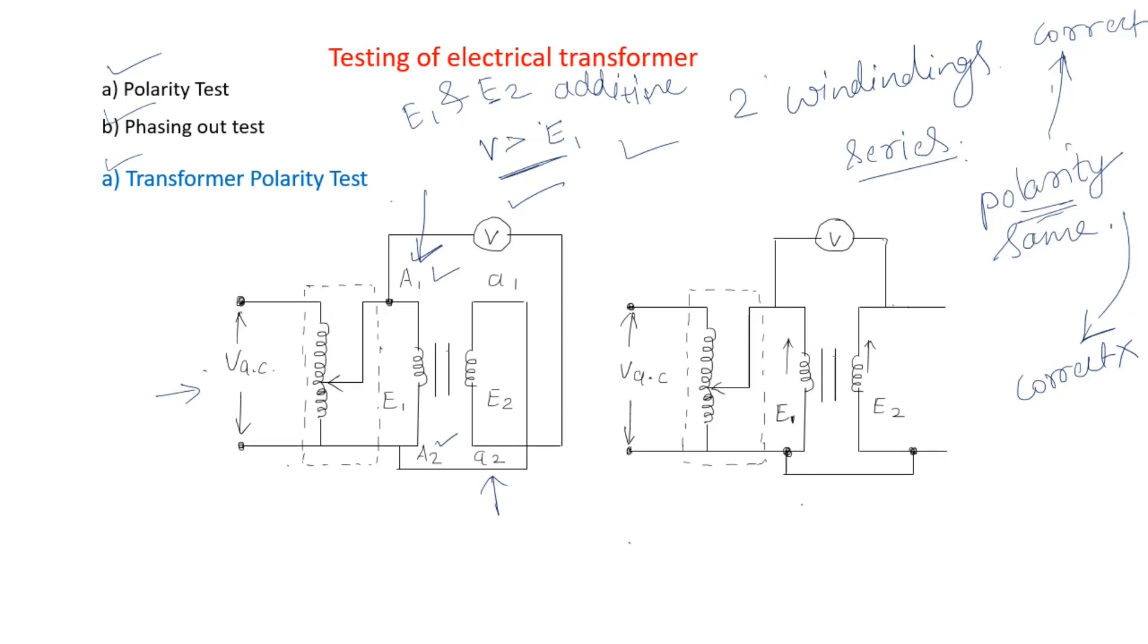So to confirm the correct polarity, in this case V should be less than E1. So in this case, to confirm the correct polarity, V should be less than E1. This is how we carry out our polarity test.